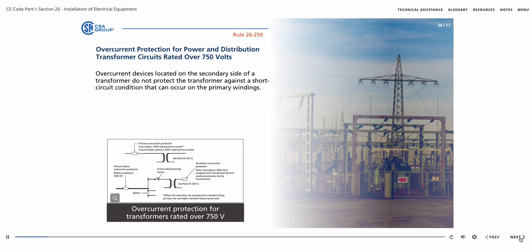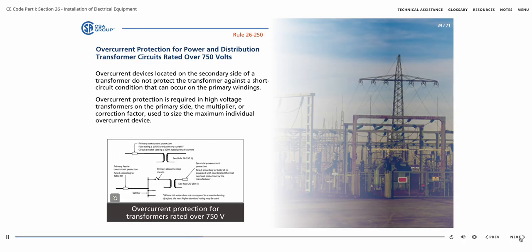Overcurrent devices located on the secondary side of a transformer do not protect the transformer against a short circuit condition that can occur on the primary windings. Consequently, overcurrent protection is required in high voltage transformers on the primary side. The multiplier or correction factor used to size the maximum individual overcurrent device.